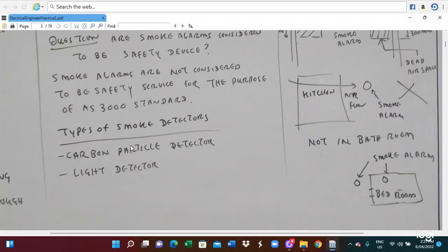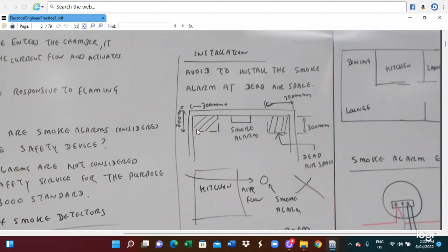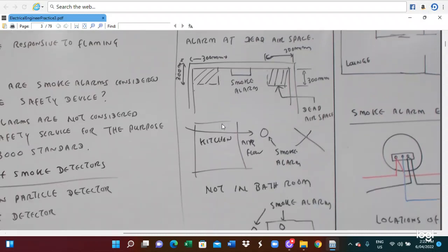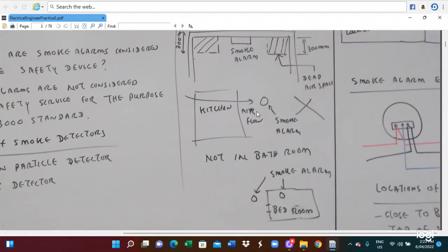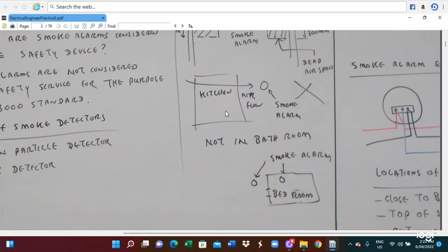In this case, the type of smoke detector is a carbon particle detector and a light detector system. Then we have to install the smoke alarm system, avoiding the dead air zone. This is the dead end, within 300 millimeters. This is the dead zone. We can install the smoke alarm system elsewhere. Also, we cannot install it in the airflow coming from the kitchen, because the smoke alarm will sense smoke from the kitchen. And it cannot be installed in the bathroom.